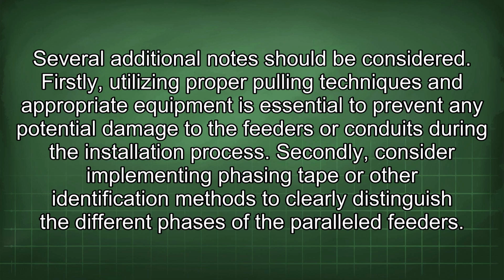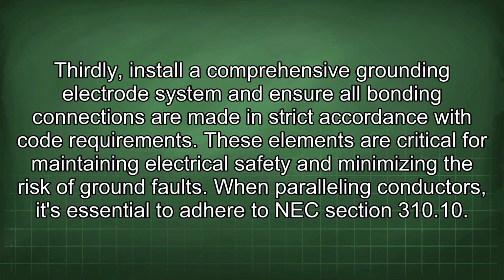Firstly, utilizing proper pulling techniques and appropriate equipment is essential to prevent any potential damage to the feeders or conduits during the installation process. Secondly, consider implementing phasing tape or other identification methods to clearly distinguish the different phases of the parallel feeders. Thirdly, install a comprehensive grounding electrode system and ensure all bonding connections are made in strict accordance with code requirements. These elements are critical for maintaining electrical safety and minimizing the risk of ground faults.